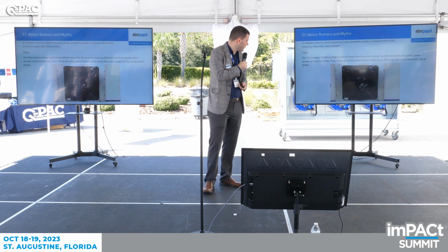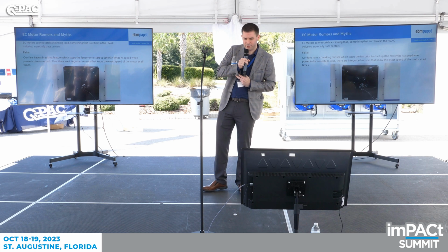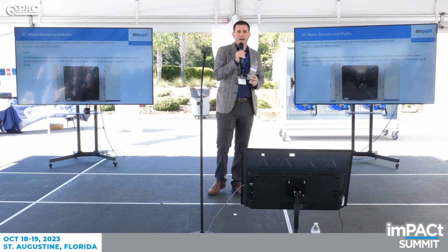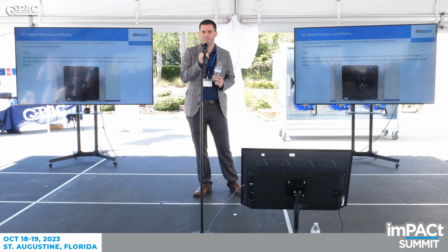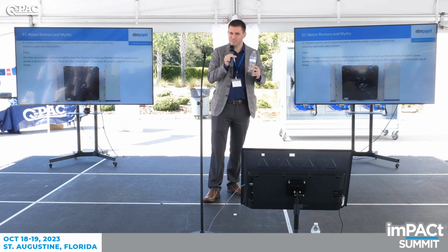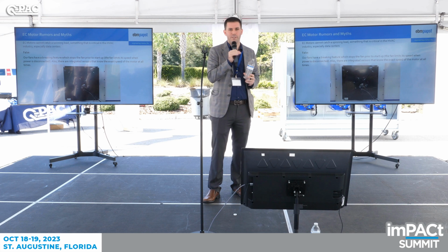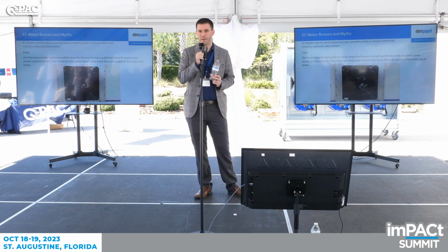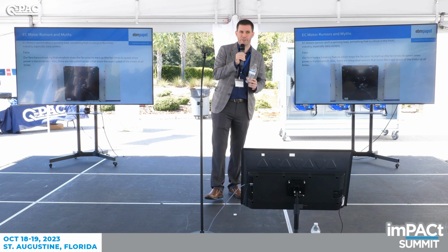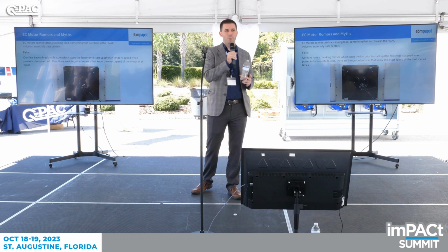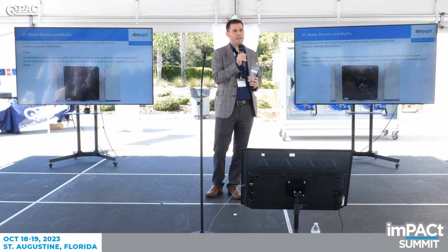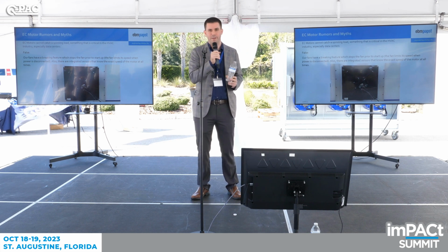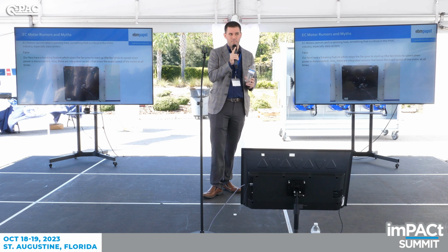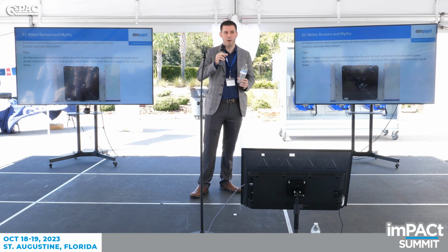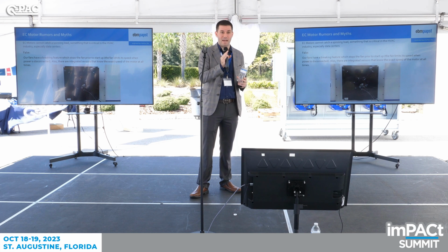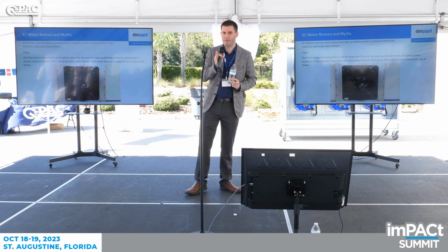Also, this video might be a little tough to see, but I could just describe it. So I mentioned that brake that's built into the fan. This is a condenser fan, though. Let's say that you're on the top of a roof and the wind's blowing really strong and the fan's now spinning in the wrong direction. And that condenser's off and you want to turn it on. With the AC fan, you won't be able to turn it on, right? Because it's spinning in the wrong direction. It can't actually torque up and spin the right direction. The EC fan will actually notice it's spinning wrong when the power is applied, apply the brake, so it'll go to a stop, and then it will ramp up the speed from there.